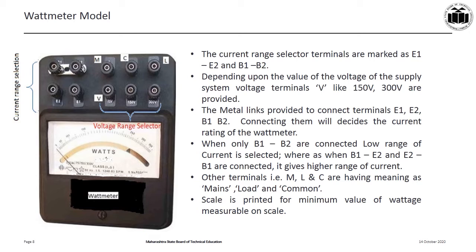Generally, the wattmeter is manufactured with a minimum of 2 ranges of voltage selection terminals, having ranges specified on those terminals, like 300 volt and 600 volt. According to the supply voltage and load rating, the appropriate range of 300 volt or 600 volt is to be chosen. Similarly, to choose between two available ranges for current, the user has to select the required current range.